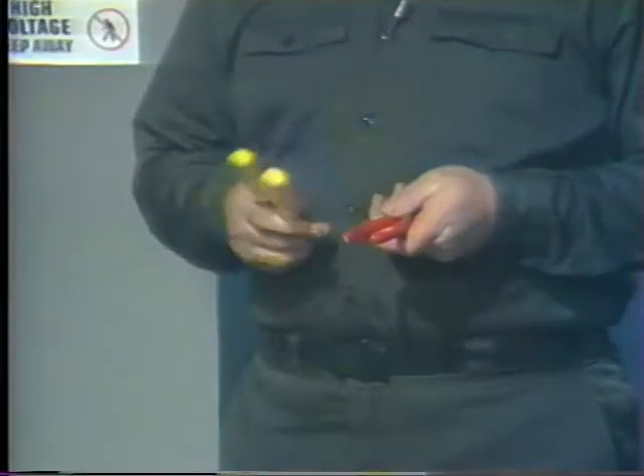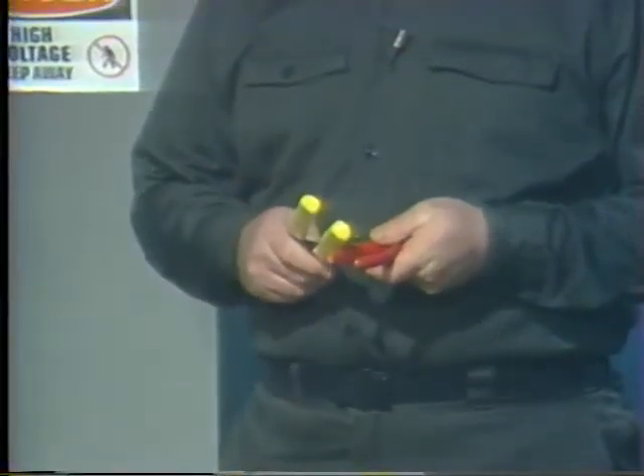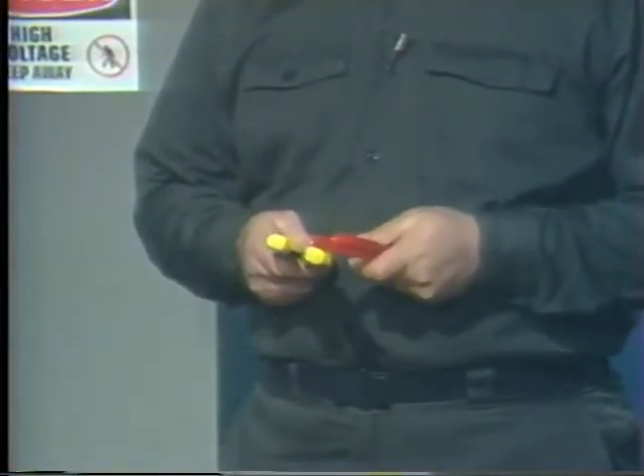When you're working on or near energized circuitry, you need special protection from electrical shock. Tools like these with insulated handles just aren't good enough. This type of coating is strictly for comfort. The plastic isn't rated for electrical resistance. So, when you're working around energized equipment, you need a better kind of insulation.